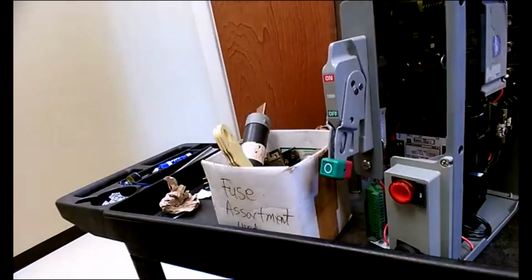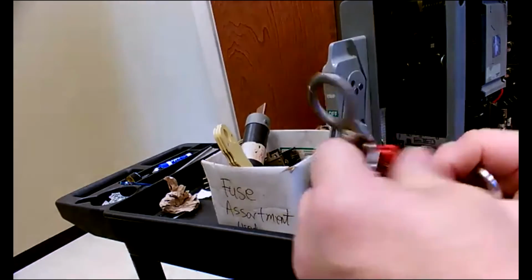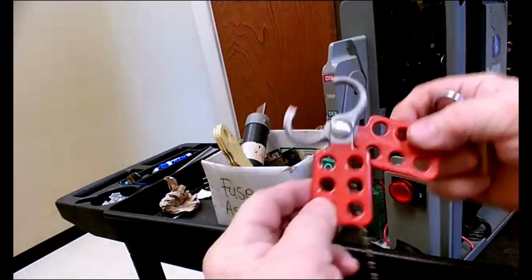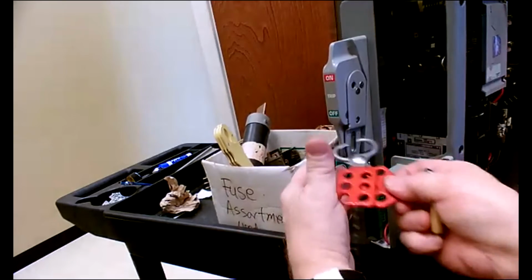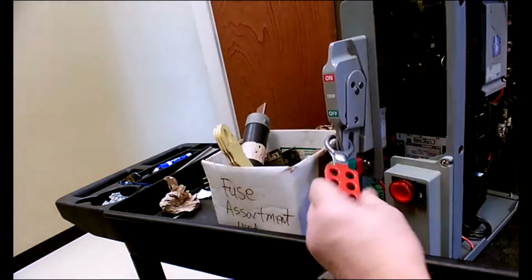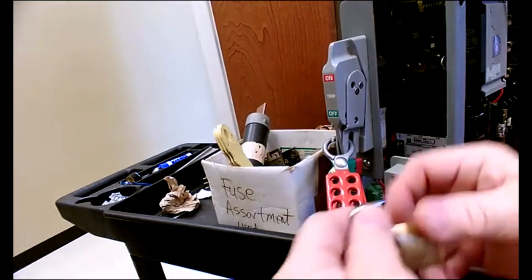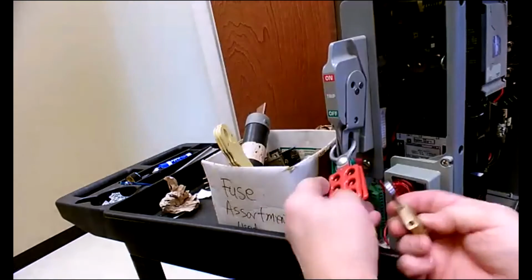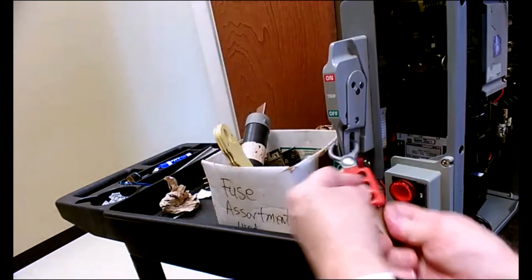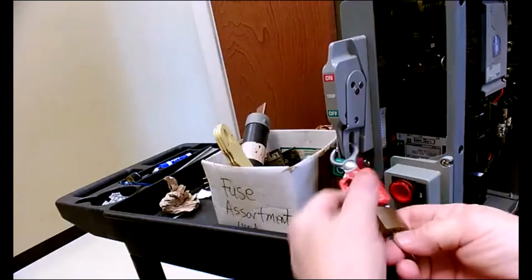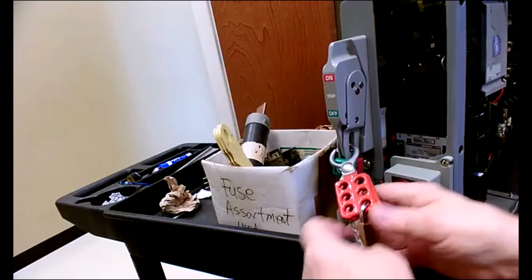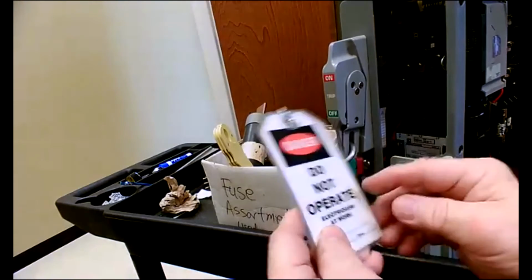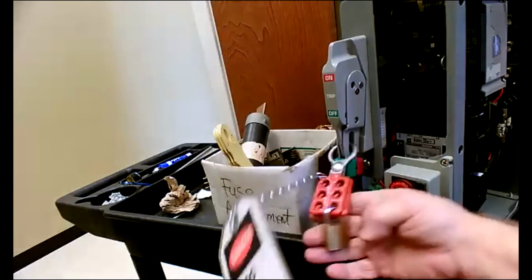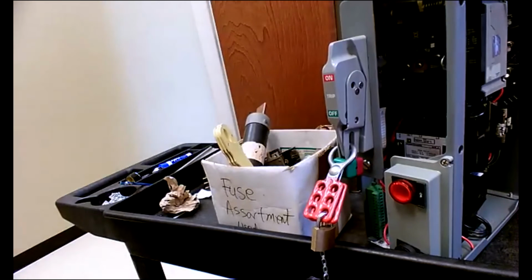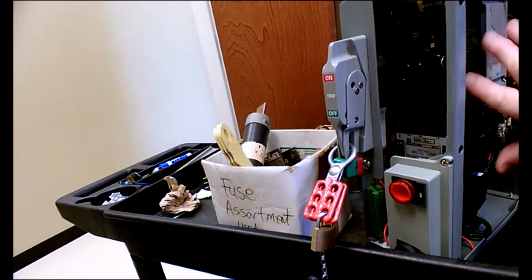Now, the next step you're supposed to do is this. You're going to take a lockout device like this and put it around the switch like that. Then you're going to take your lock and put your lock around that. You pull the key out. That key's yours. Nobody else gets it. That tag is going to have your name on there, and nobody's got a key but you. Then you want to test voltage and see if it's dead.